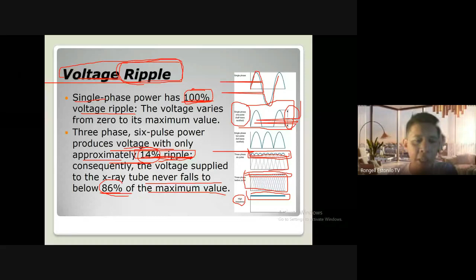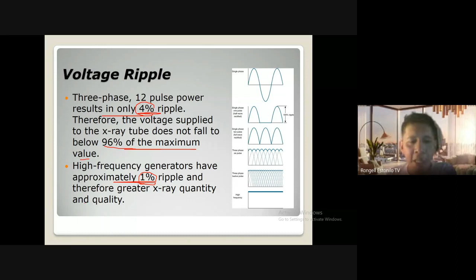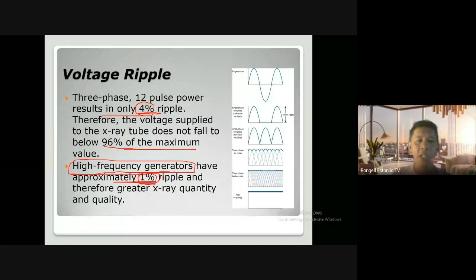And for high-frequency generators, approximately 1% voltage ripple, and therefore greater X-ray quantity and quality, kasi 99% of its value are useful in X-ray production. Dito mas makikita ang advantage ng iba't ibang generator - mas maganda talagang gamitin ang high frequency generators. The most efficient method of X-ray production also improves the waveform with the lowest voltage ripple.